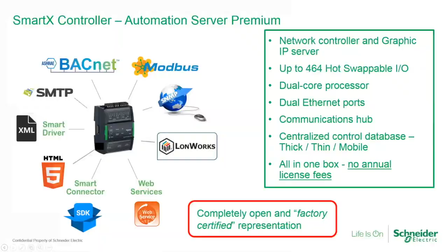That dual Ethernet port runs a Cat5 cable to our field controller, so we have IP-enabled field controllers. We just match the point count to what's required of that piece of equipment—there are 7 and 9 point count field controllers for VAV boxes, and 15, 18, 24, and 36 point controllers applied to fan coil units, chiller plants, or whatever—then we run that Cat5 cable to those.